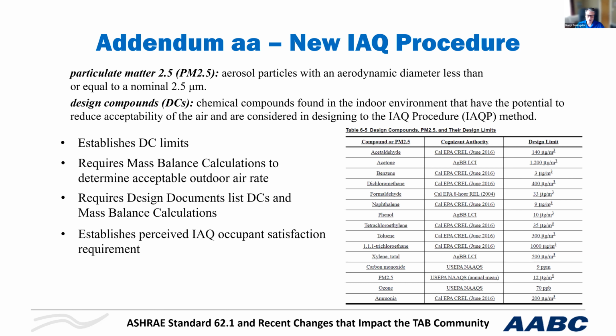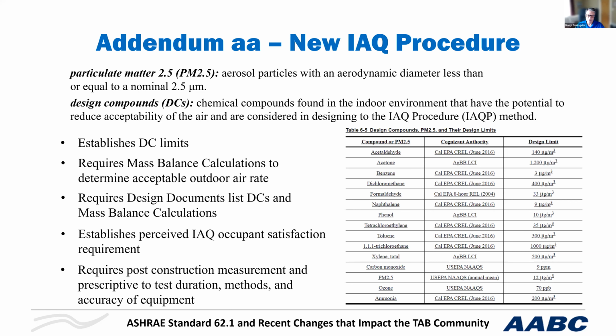An interesting thing that they're doing now in this standard is requiring a subjective test afterwards, asking the occupants, does the air seem good to you? I hope so when you engineer the system this way, that it's going to. But furthermore important, there's going to be a post-occupancy test requirement, and it's very prescriptive as far as the test duration, the equipment that's used, and the methods that you use to determine this.